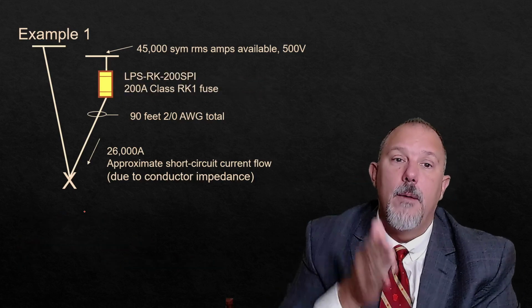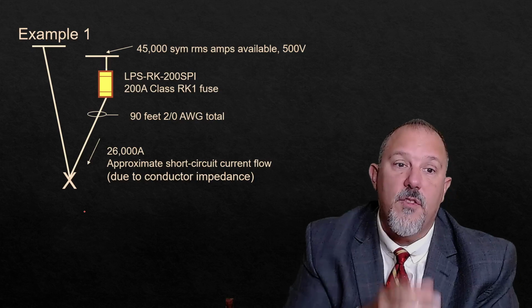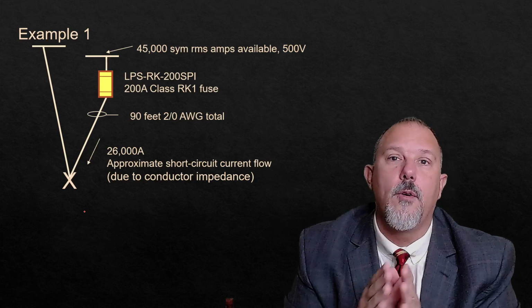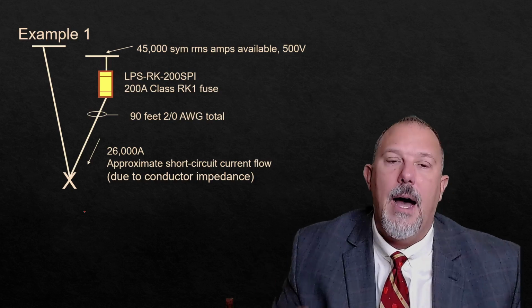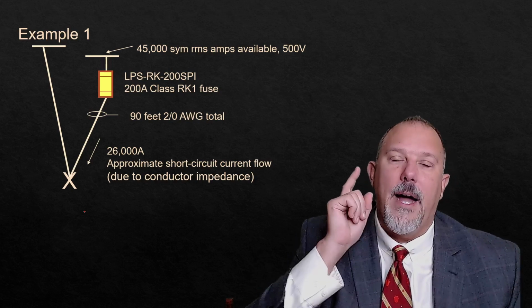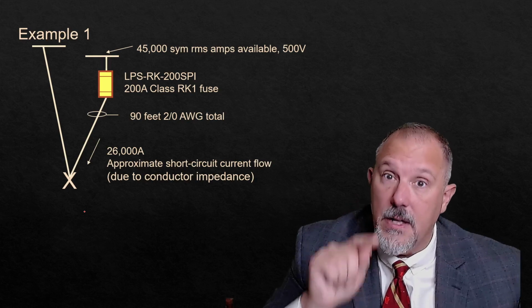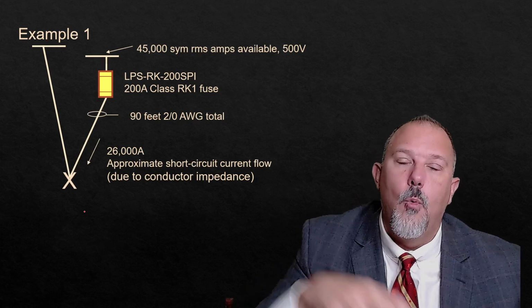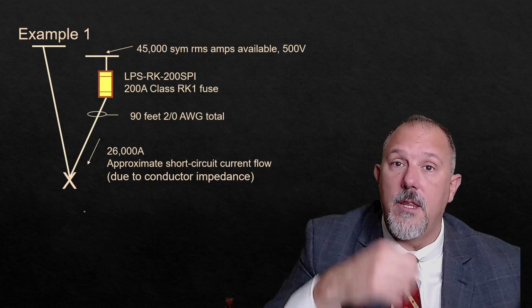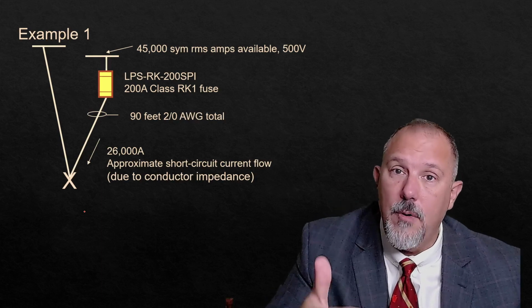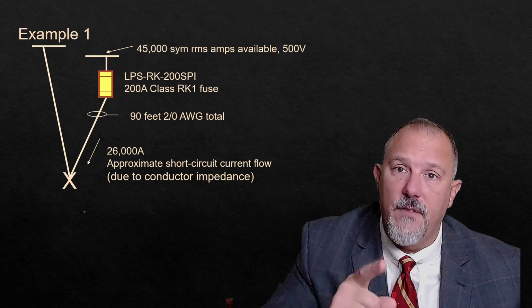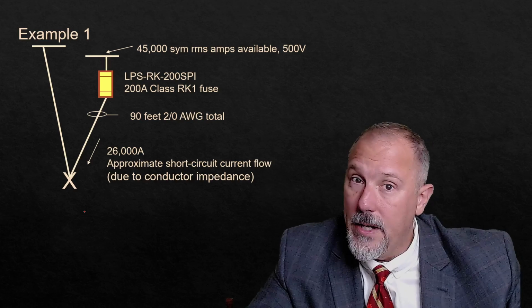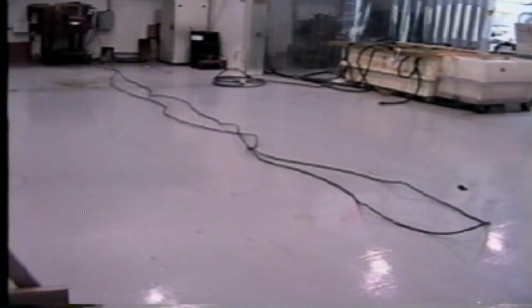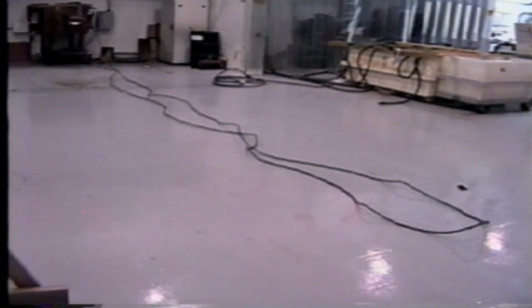We're going to do the exact same test now. We're going to put a 200 amp class RK1 fuse, current limiting, with 26,000 amps flowing through it. We know we're well into the current limiting region of the fuse. I'm going to show you the same example. I need you to watch very closely at the tip of the conductor. This demonstrates what current limiting does in reducing the force and heat throughout the power distribution system when a device operates in its current limiting region. Here we go. I hope you caught that.